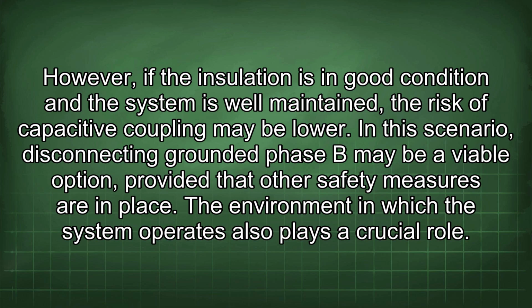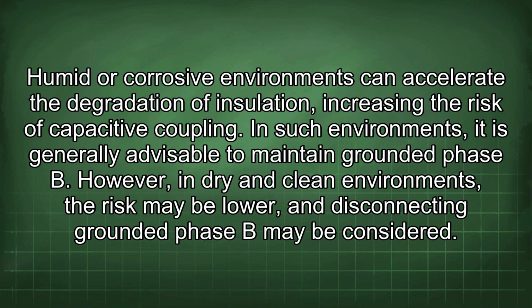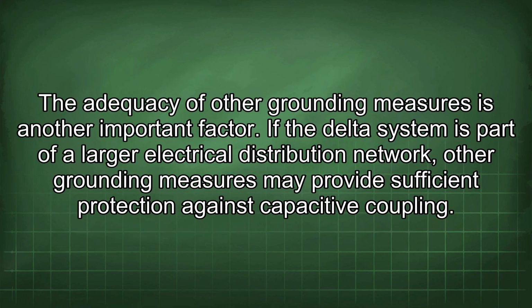The environment in which the system operates also plays a crucial role. Humid or corrosive environments can accelerate the degradation of insulation, increasing the risk of capacitive coupling. In such environments, it is generally advisable to maintain grounded phase B. However, in dry and clean environments, the risk may be lower, and disconnecting grounded phase B may be considered. The adequacy of other grounding measures is another important factor. If the delta system is part of a larger electrical distribution network, other grounding measures may provide sufficient protection against capacitive coupling.